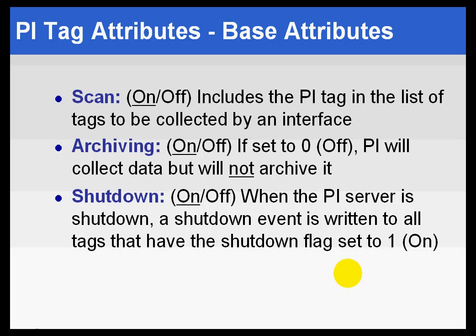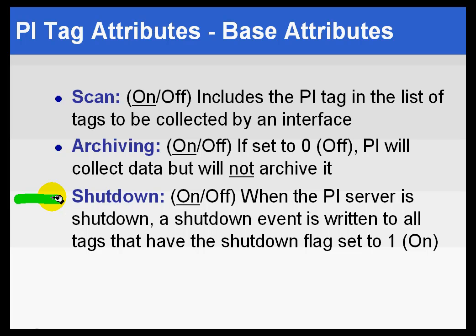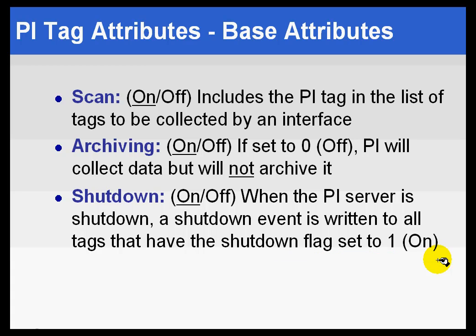Lastly, there are some attributes that can control some fundamentals and are pretty self-explanatory. For example, with scan equal to On, it simply means we are going to be actively scanning this tag by whatever interface or application is writing to it. Scan Off would effectively shut down the interface without deleting it. Archiving turns on and off whether we archive the data. And Shutdown works this way: whenever the PI Server is shut down, a shutdown event — which is a digital state — is written into the archive for all tags that have the shutdown flag set equal to one. There are other mechanisms for indicating that on the interface level, and we'll discuss how to set up these shutdown notifications later on.